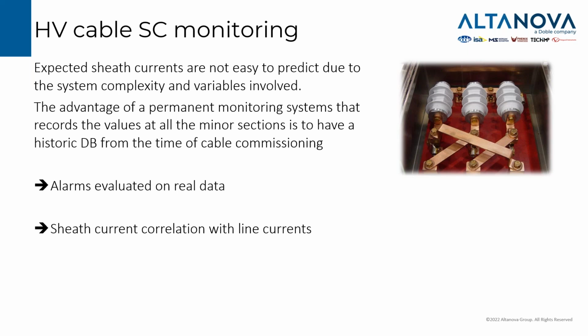A very good information comes instead from a permanent monitoring system, where we have all the sheath currents recorded and trended. We can correlate the historic values with an alarm, and we can as well correlate the recorded values of the sheath current with the line currents. That is a big impact on the sheath currents themselves.